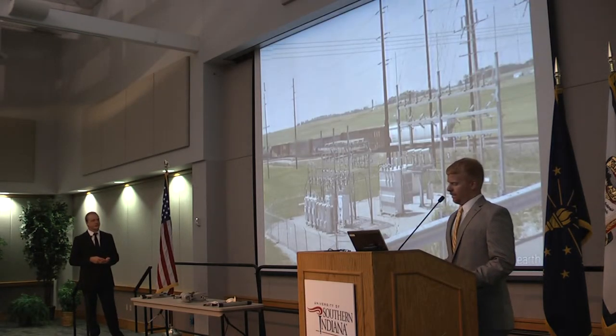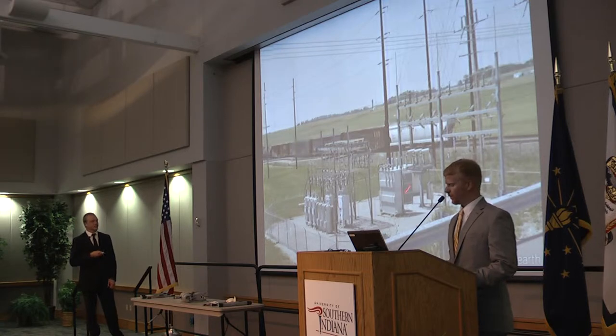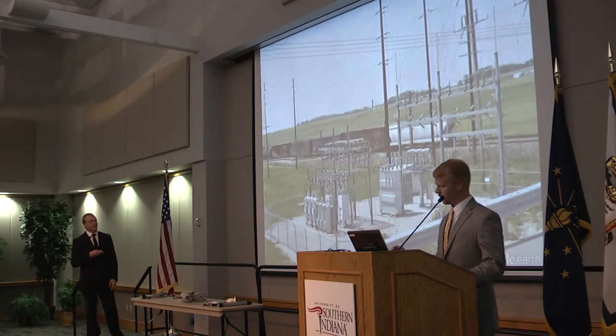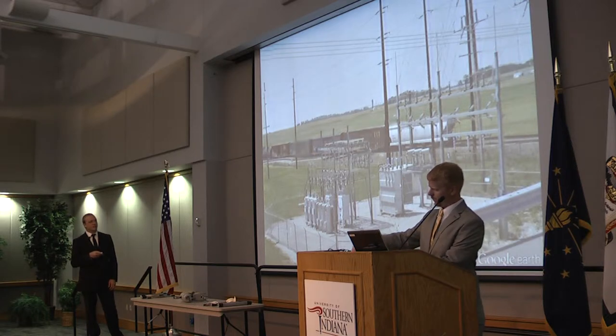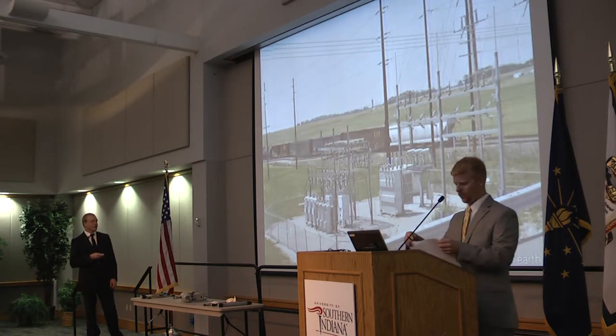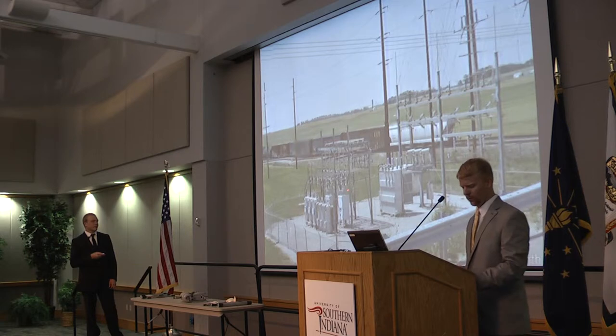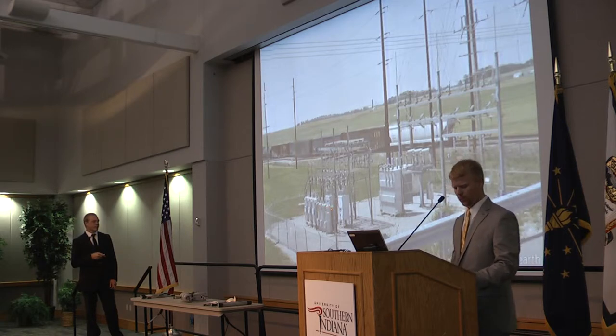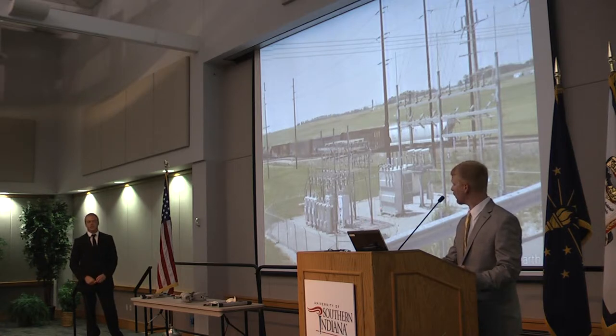This is an up-close shot of our substation. This is the existing transformer, circuit breakers, and regulators. The 69,000 volts comes in here and gets stepped down by the transformer. It's monitored through these voltage regulators and goes off towards Azteca and north in the surrounding area. And our goal here is to add a third exit to give Azteca a dedicated circuit.